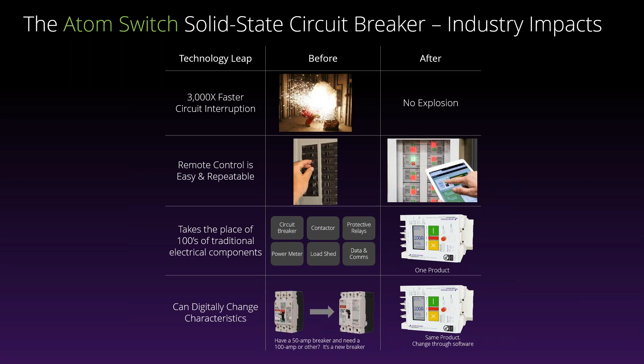It takes the place of multiple devices, where before you might have a circuit breaker and a contactor and a relay and a meter and a data and communication device, all of that you'd have to get an aggregator to come in and pull it all together for you. Now it's all in one device. And instead of having a different SKU for every single current rating breaker, you don't need to buy a 20 amp and a 50 amp and a 100 amp. You buy one device and program it to whichever protective rating you need it to be at.